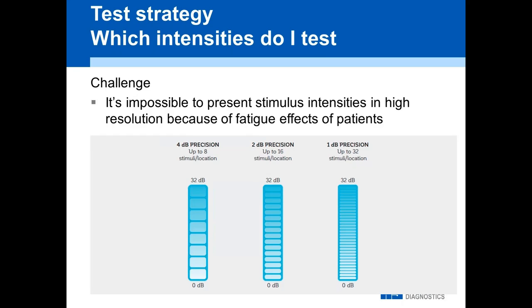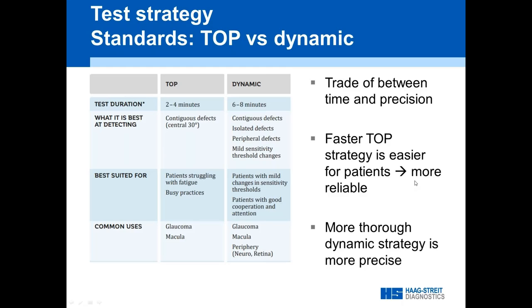Which intensities do you test? The same problem as with spatial extent — we have to compromise. The most commonly used strategies are either TOP or Dynamic. Both have their merits as it's a trade-off between test time and precision. From a purely mathematical point of view, the Dynamic strategy — taking six to eight minutes — is more precise, really better at finding subtle isolated defects. For the majority of defects, it doesn't matter so much.